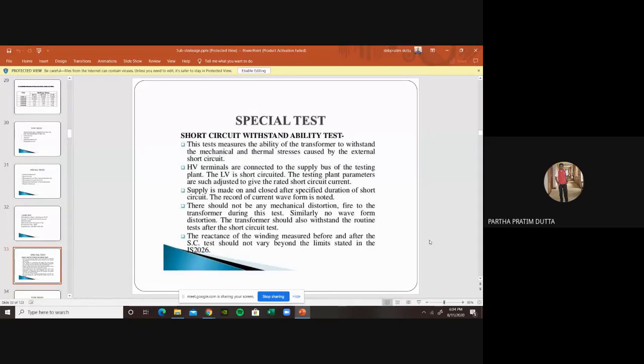Now we come to the short circuit withstand test as a special test, as I told you. This test measures the ability of the transformer to withstand mechanical and thermal stress. When the short circuit current flows, a huge stress is developed in the transformer because of the high current and magnetizing force. Although the short circuit period is very short, we see whether the transformer is capable of withstanding the mechanical and thermal stress developed.